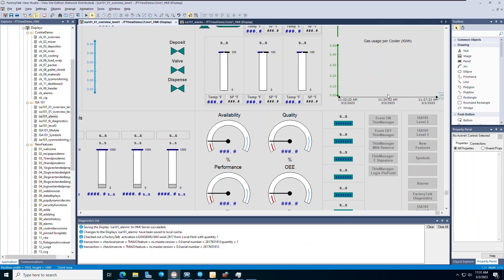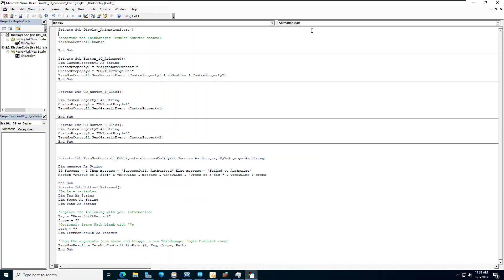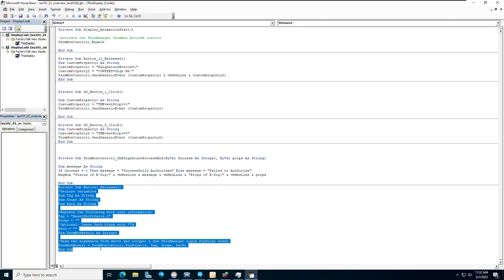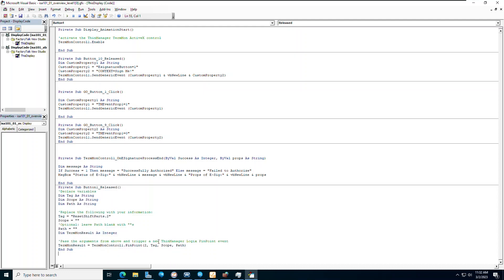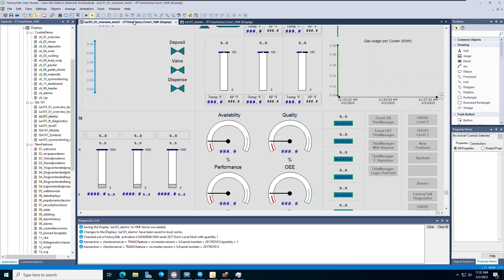From here, right-click and open the associated VBA code. We need to make sure the TermMon ActiveX control is activated whenever the FactoryTalk View SE display is called. Refer to the ThinManagerLogix Pinpoint white paper for additional VBA code if needed. Look for the subroutine with your button name — in this case button 1 — with the action released. This can be changed if needed at the top of the window. Be sure to save your VBA code after making any changes, then save your displays in FactoryTalk View Studio. You are now ready to launch your Pinpoint application in ThinManager.